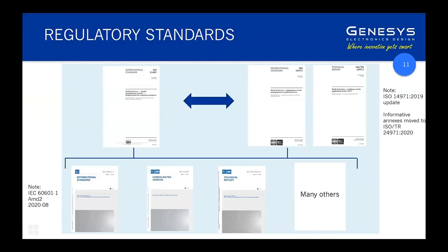So having a bit more look at the regulatory standards that apply, and I use a similar presentation to the slide to this and other presentations to show the key headline medical standards that we'll be dealing with. And the linchpin is ISO 13485, which is the quality system standard, and ISO 14971 is the risk management standard, goes arm in arm with that.